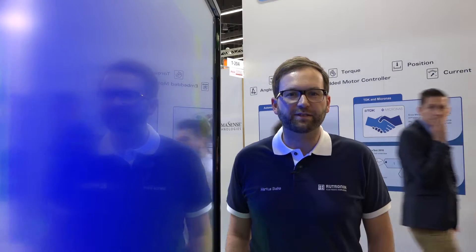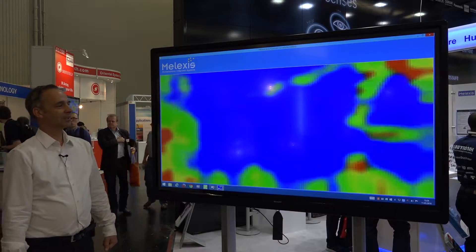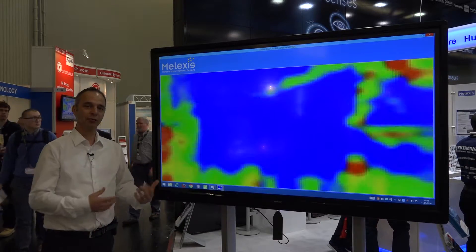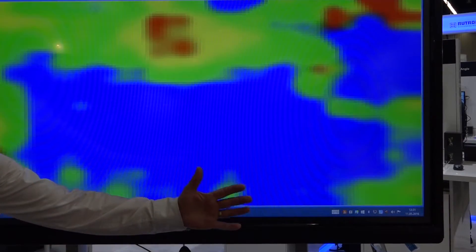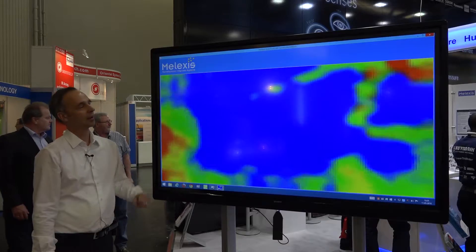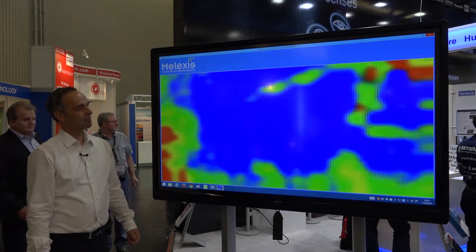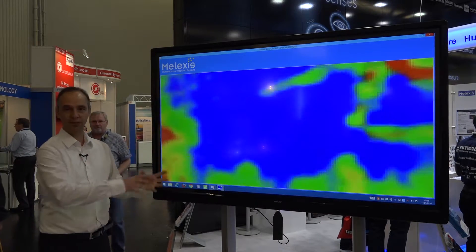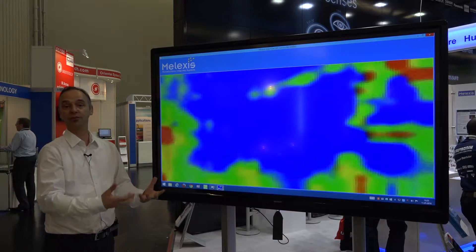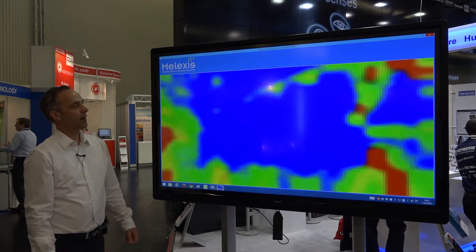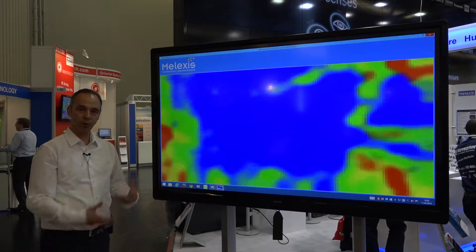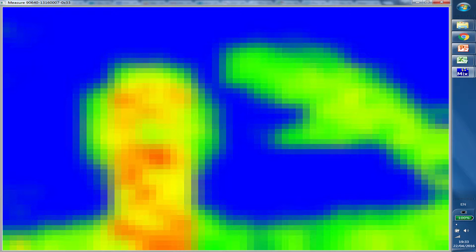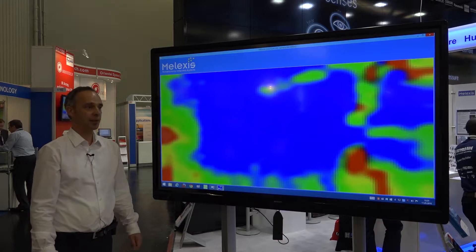Which are its main applications? There are multiple applications for this device. It actually senses the absolute temperature. This means that it can be used in the industry and process industry to look at the temperature of the process, the temperature for instance of food. But we also see it is more and more used as a presence detector to see if there are people present in the rooms for building automation kind of applications.